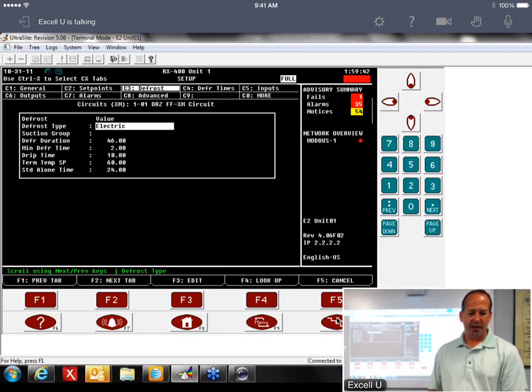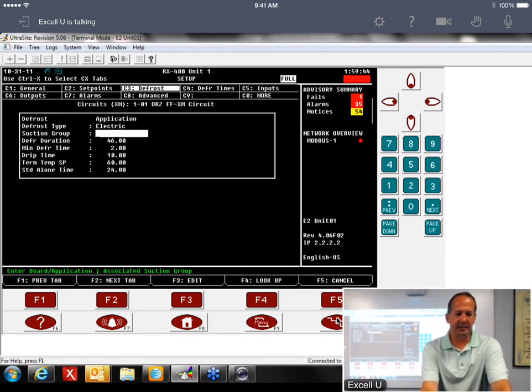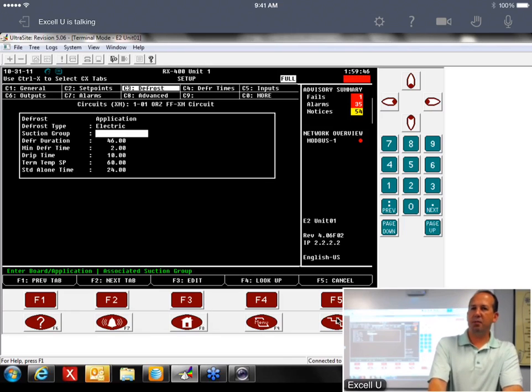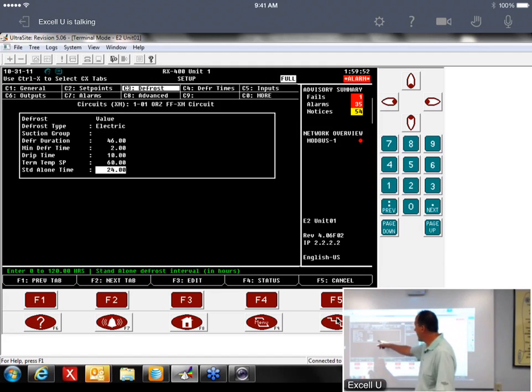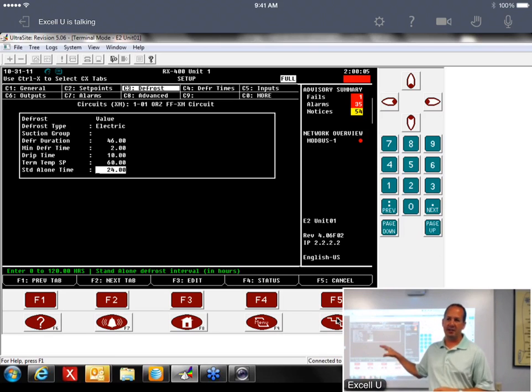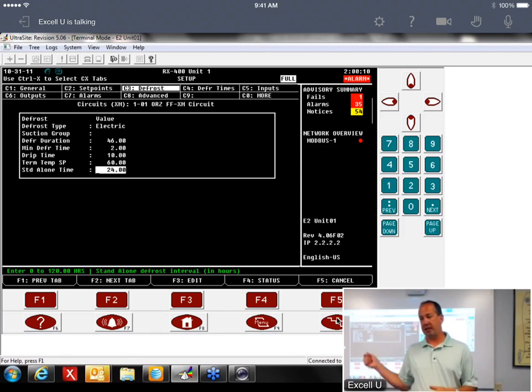Okay, your defrost setup here. This is the same as all your other circuits for defrost. But there is this one added feature down here: standalone time. So the Dixell device itself does not have a clock. It does not know that, hey, it's Saturday at 2 in the morning and I go into defrost. That all resides in the E2. The E2 tells it, hey, it's Saturday, 2 a.m. going to defrost. The E2 is sending that signal down to the XM device.